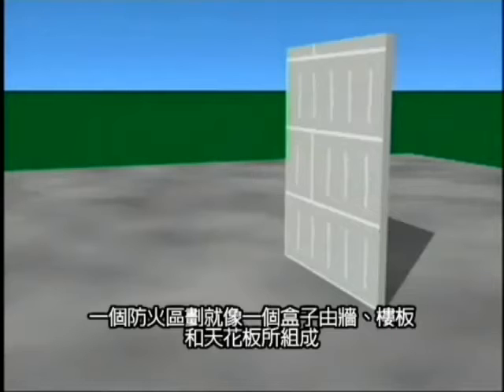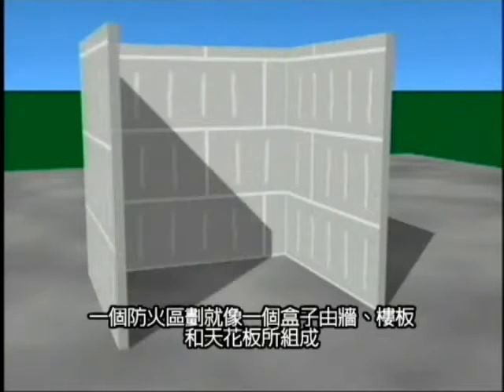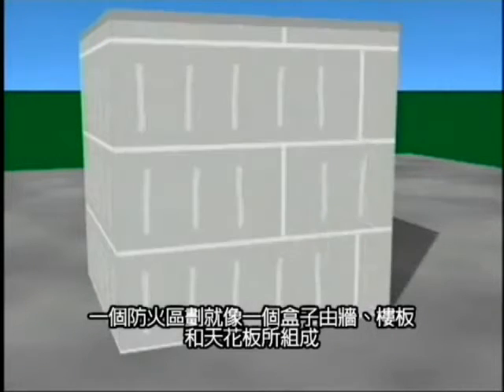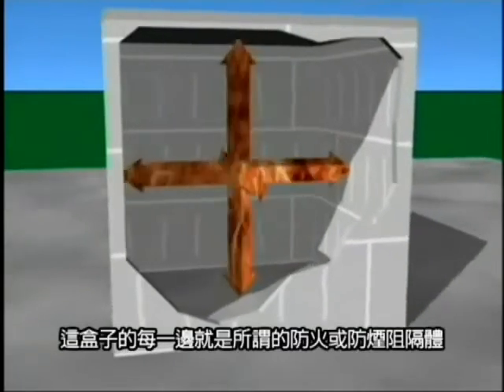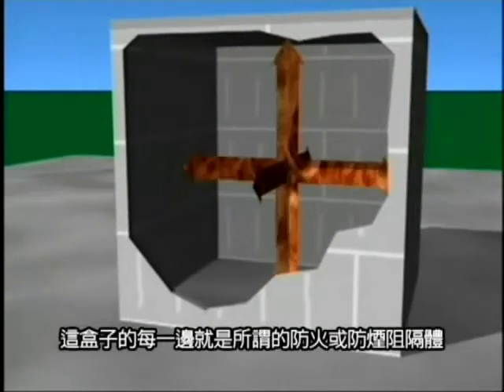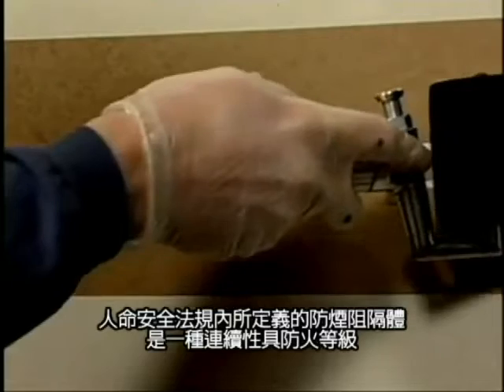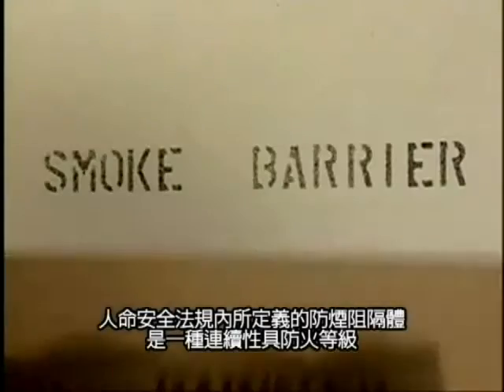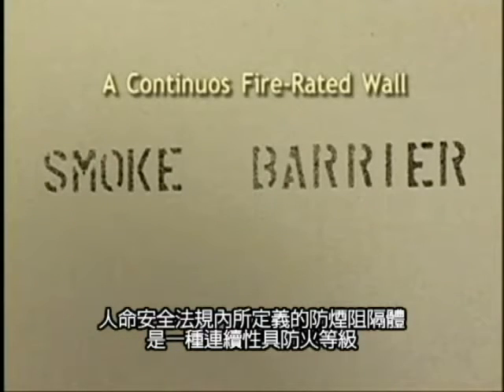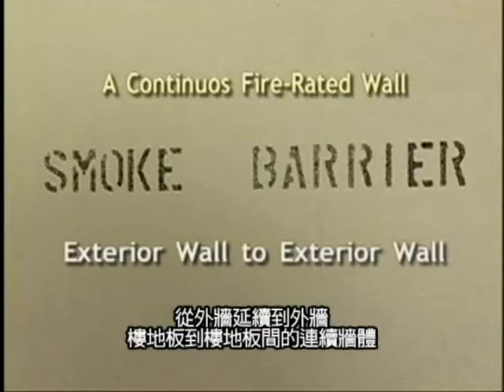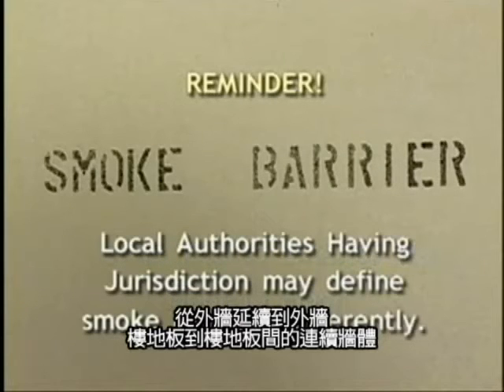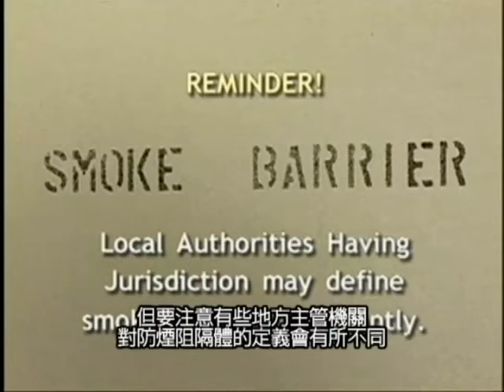A compartment is like a box made up of a floor, walls, and a ceiling. Each side of the box is known as a fire or smoke barrier. A smoke barrier is defined by the Life Safety Code as a continuous fire-rated wall that extends from exterior wall to exterior wall and floor to floor. Be careful, however, because some local authorities having jurisdiction may define smoke barriers differently.